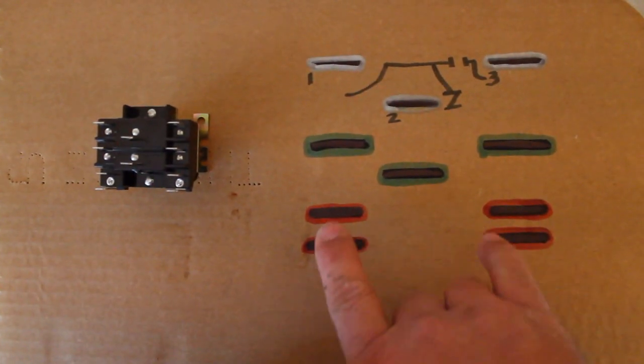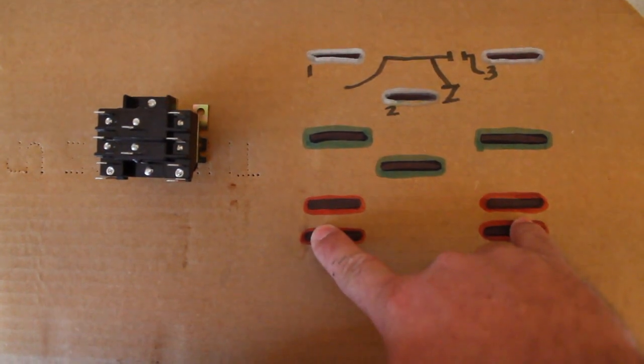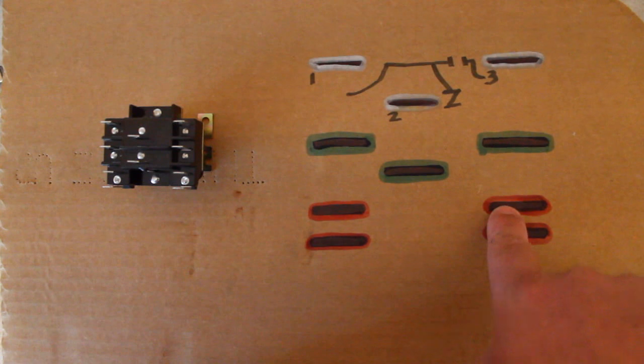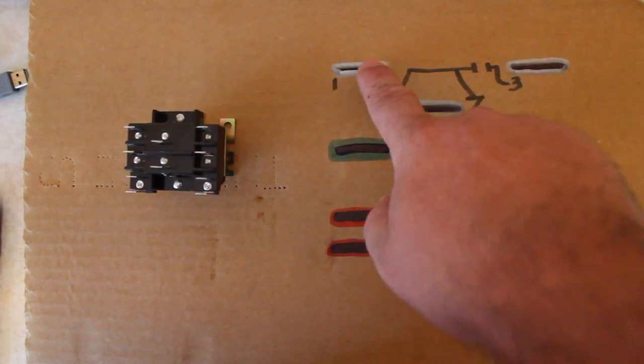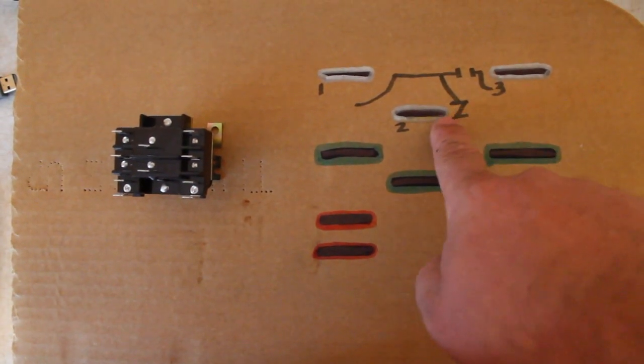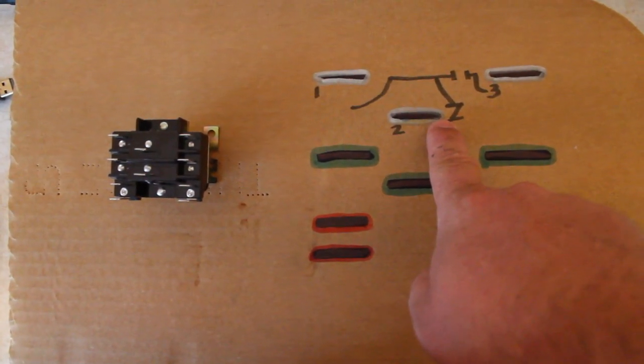What happens when there is voltage applied to the coil? We have our common and hot flowing into each side here. One side is common, the other side is hot. This normally open switch closes and voltage flows from one to three. And the normally closed switch will open.